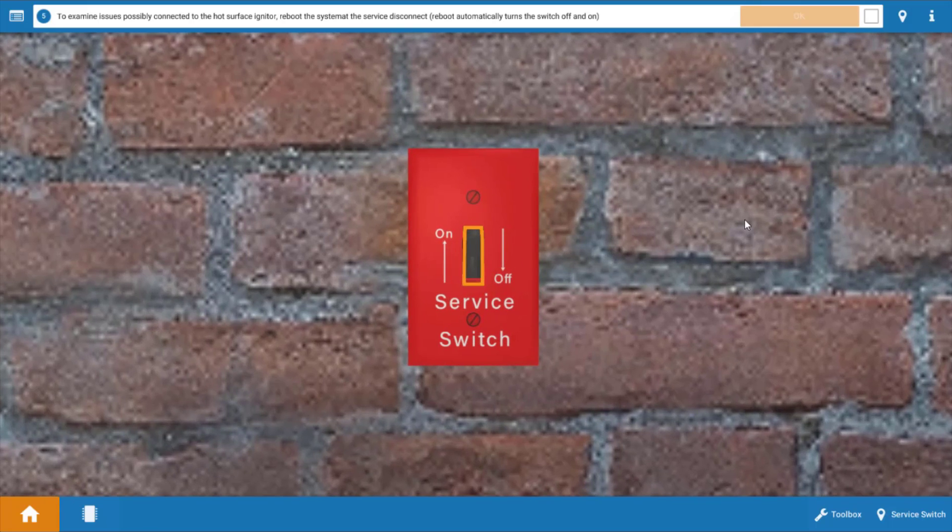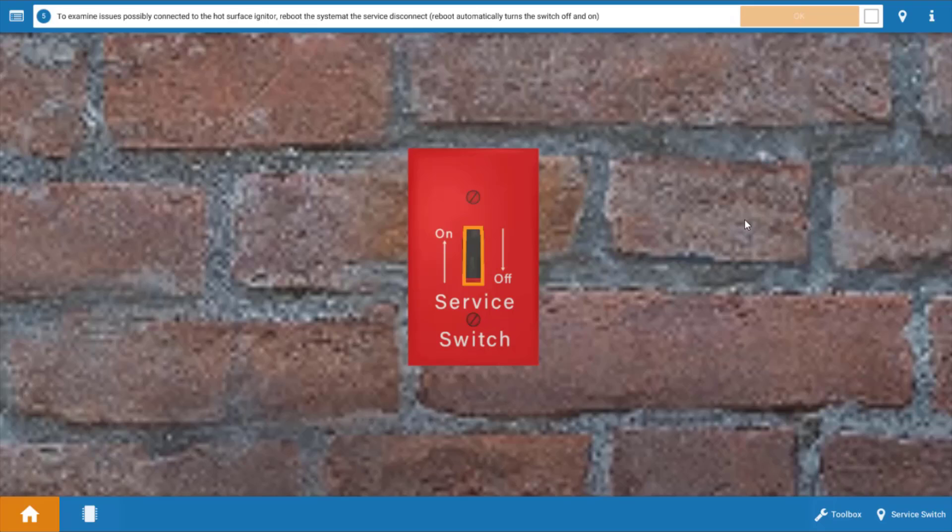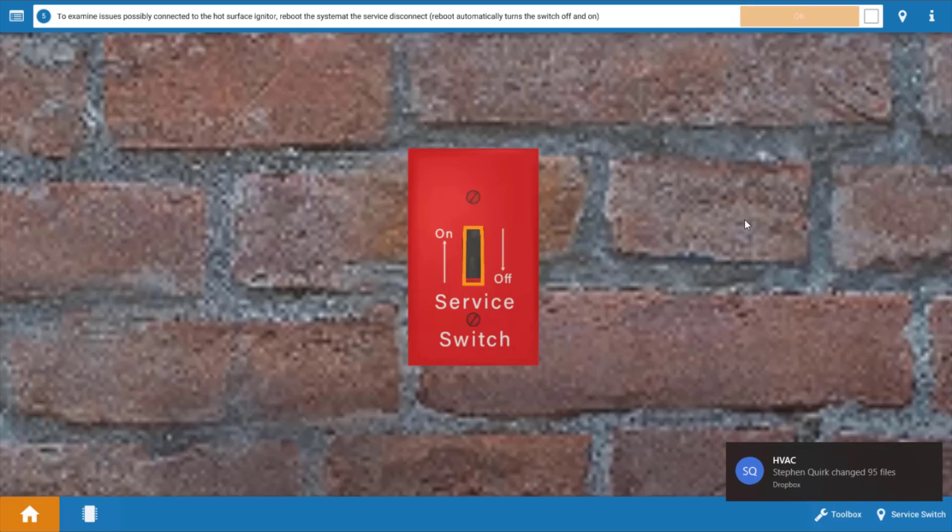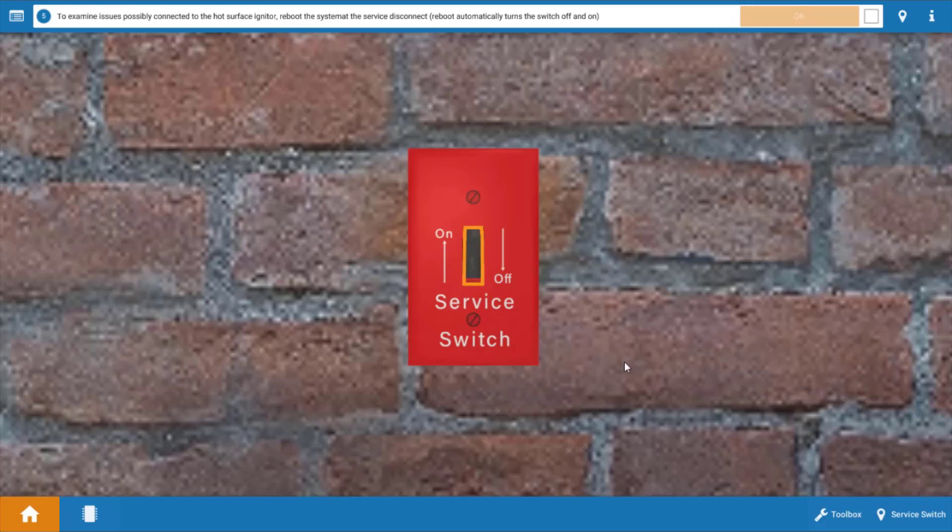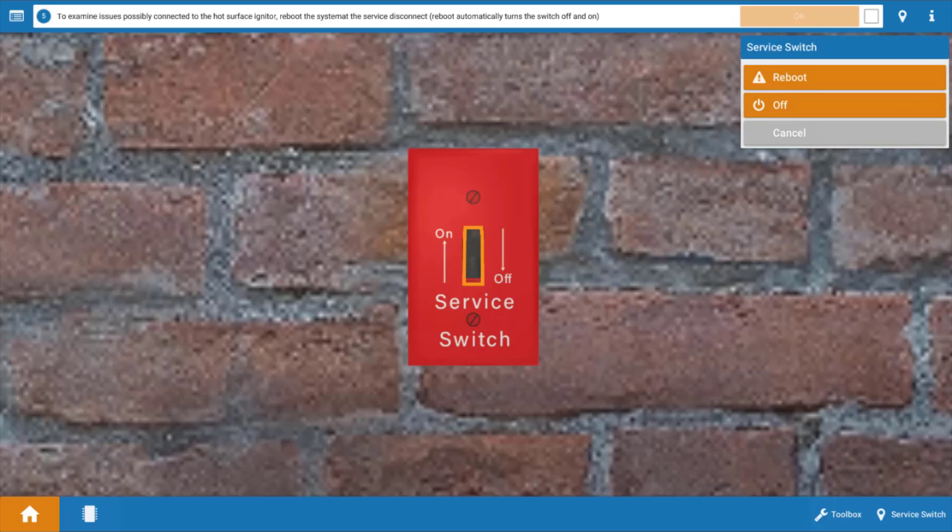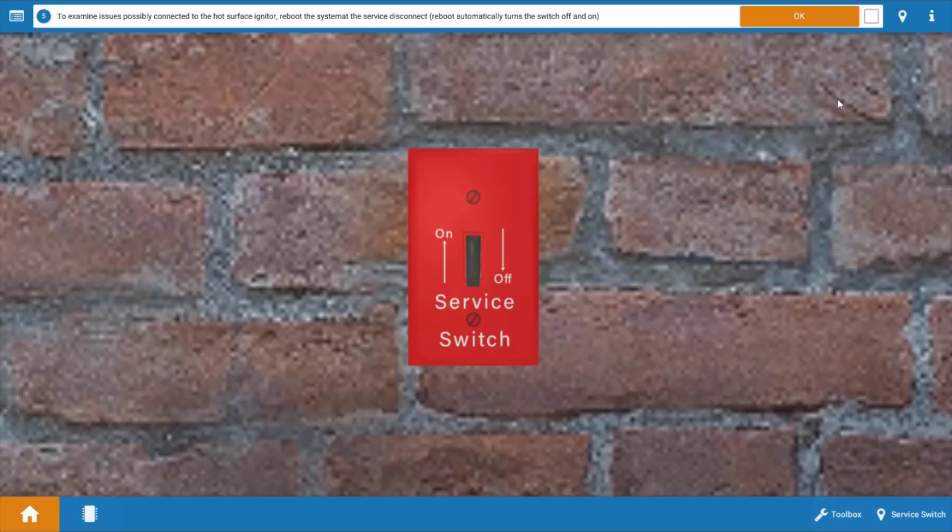Next we want to check the igniter but before we do that it probably is going to be necessary to reboot the system or turn it off and back on and this is because once three attempts at ignition have been made the IFC or integrated furnace control will lock out operation of the furnace and this can be remedied by simply turning the furnace off and back on. So we're going to click on this little orange outline and we're going to reboot the system.